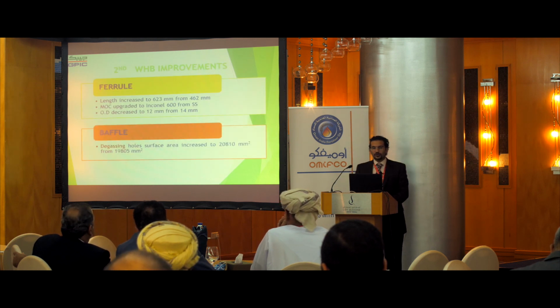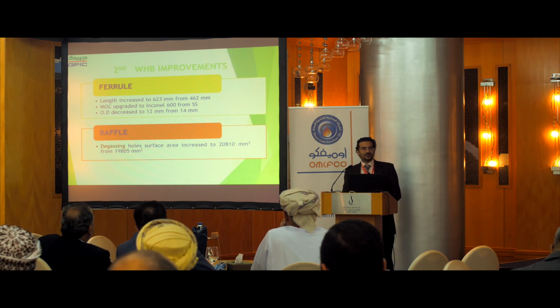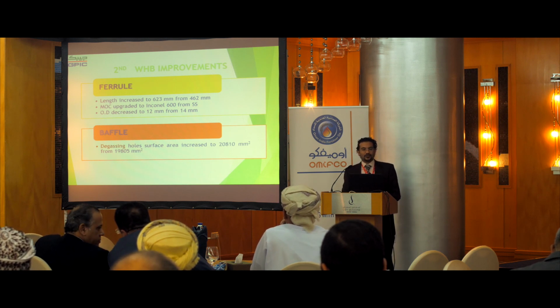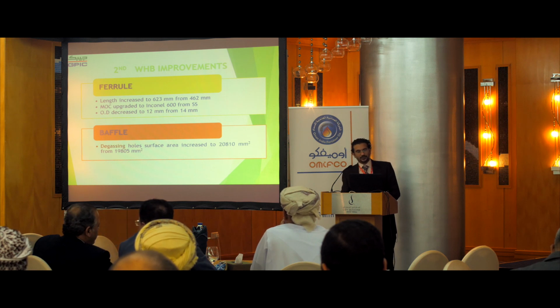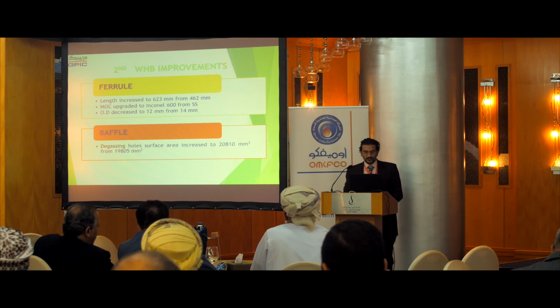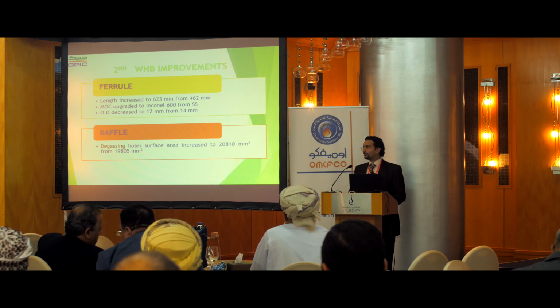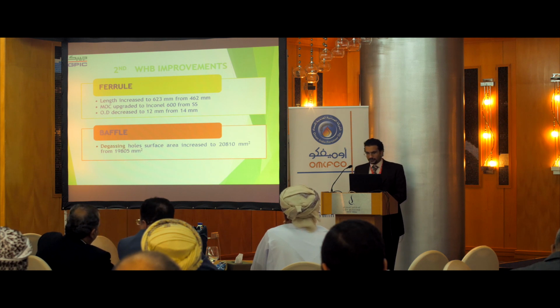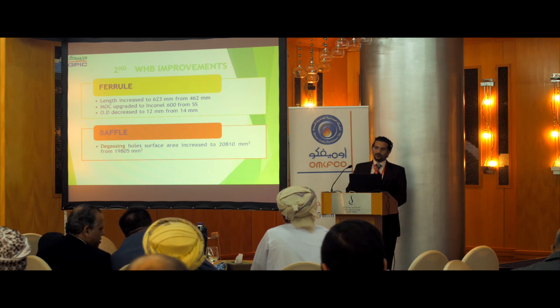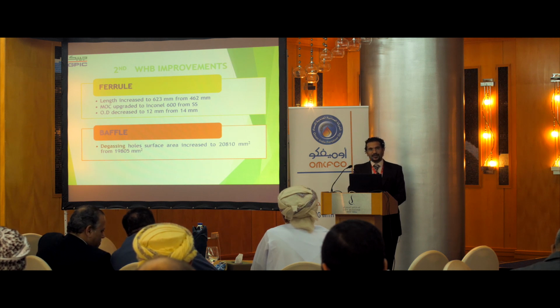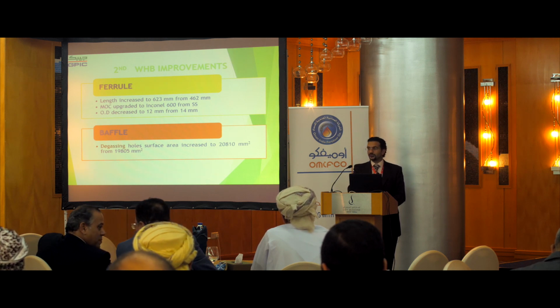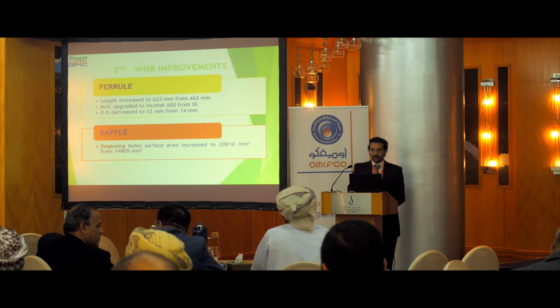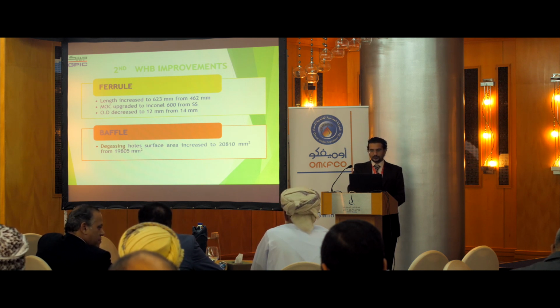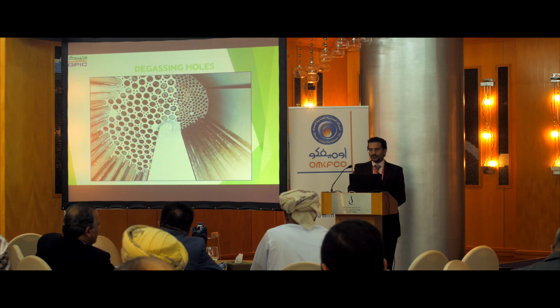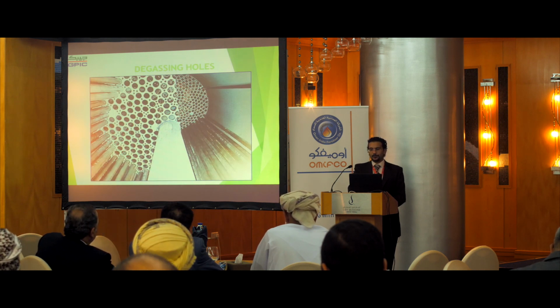For our second waste heat boiler, there had to be, of course, improvements after many years. The length of the ferrule was increased to 623 millimeters from 462. The MOC, material of construction, was upgraded to Inconel 600 from stainless steel. The outer diameter decreased to 12 mm from 14 mm. As for the baffle degassing holes, the surface area was increased to about 20,810 millimeter squared. These are the degassing holes as the steam exits.